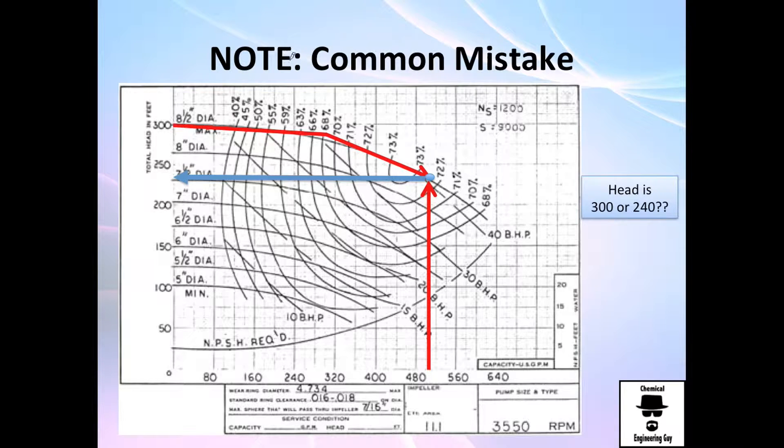I want to show you the common mistakes people do when using this diagram. So one day I was asked: if this is the volumetric flow rate and I'm using an impeller of eight and a half inches, or maybe I'm working at 72.5% efficiency, what is the head of my system? And it should be very obvious guys that you need to do a horizontal line to the left.